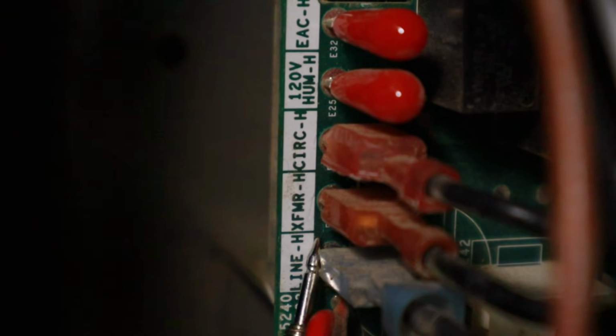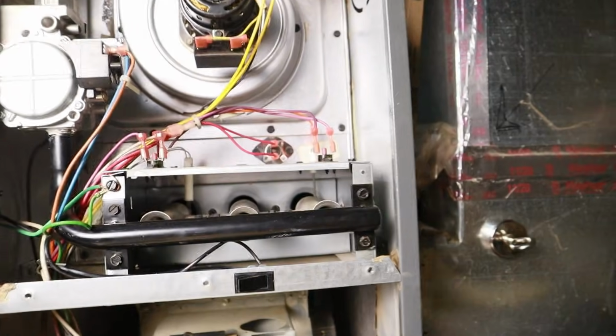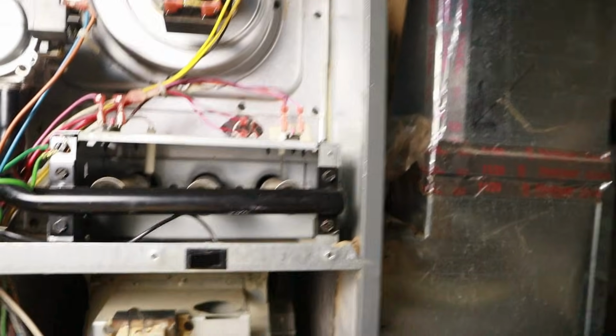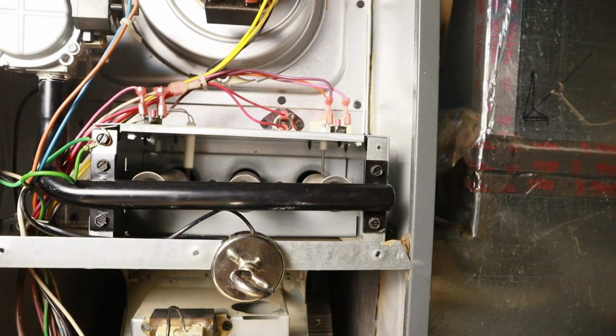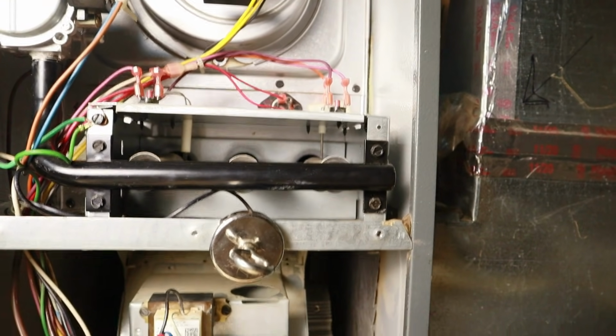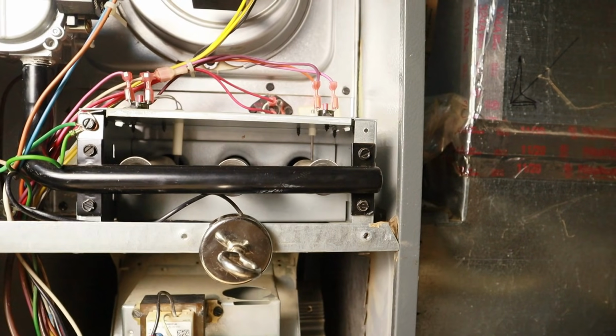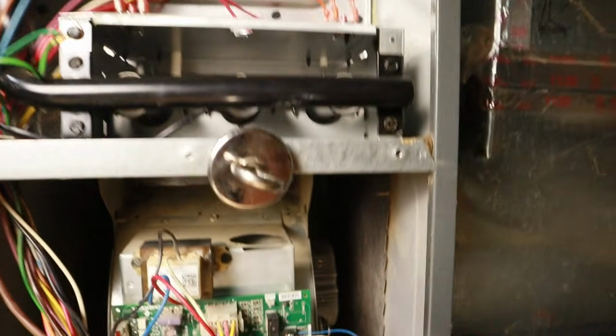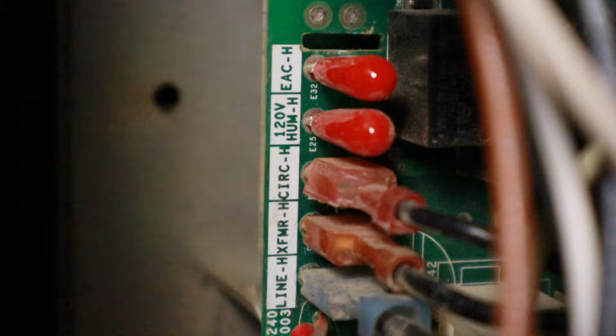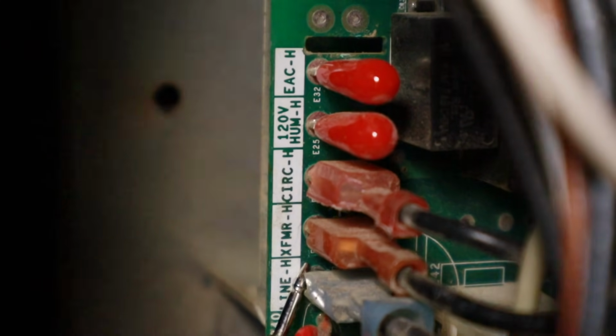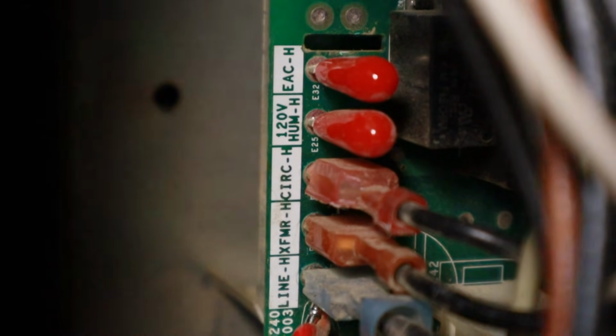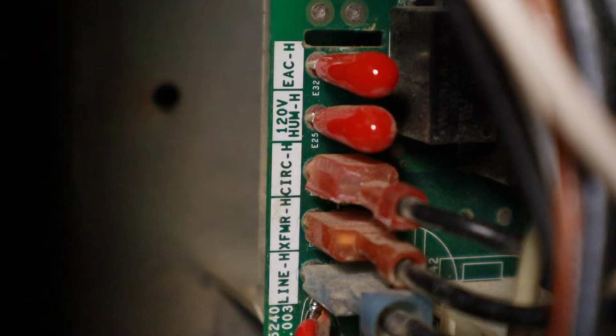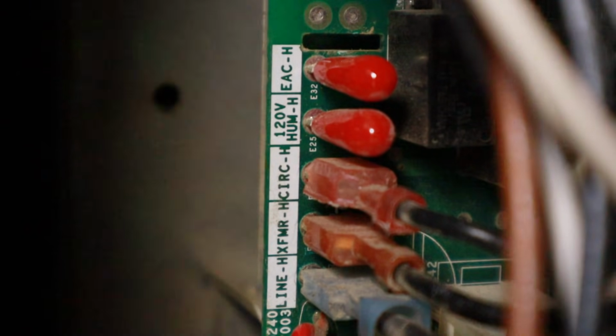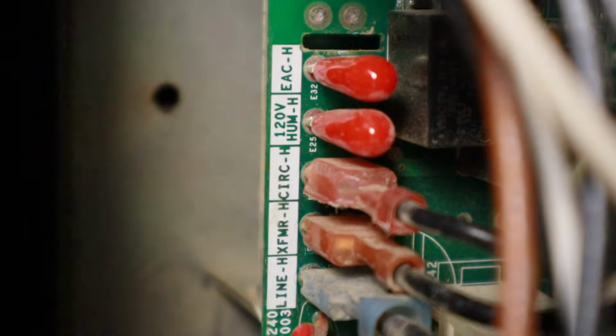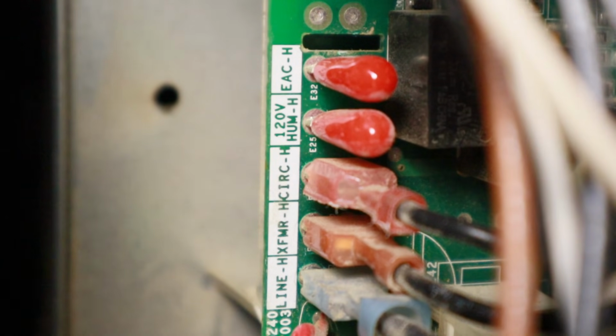And the reason why I'm not reading anything right there right now is because my door switch is actually open. So what a lot of guys will do is they'll take a magnet like this one, they'll stick it right on that door switch so that it stays closed. And now we can go back and test for power on our line H terminal on our control module. So I'll go ahead, put my probe on there, go to ground, and you can hear my multimeter beeping, which tells me I have 125 volts there. So now I know my control module is actually getting power.